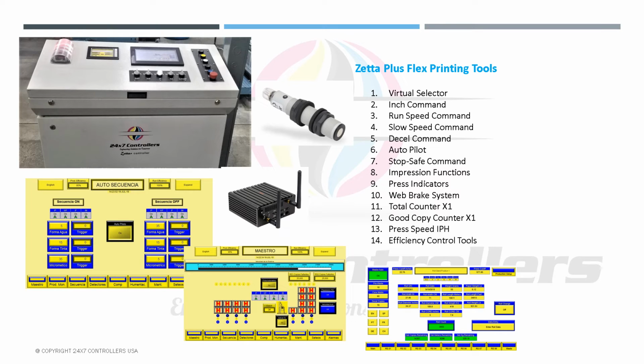Stop safe button. This button, for industrial safety issues and under OSHA standards, is offered with several new variants, for example: redundancy in the control circuits due to safety issues; controlled speed stop with deceleration curves programmed for maximum speed, typically about 15 to 20 seconds; safe final stop where the drives of the machine's motors are rendered inoperable.